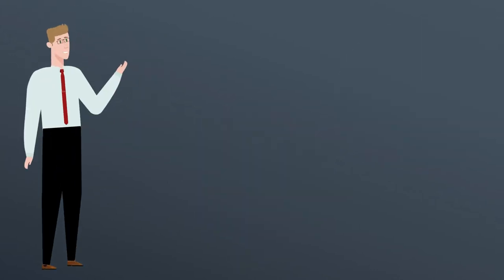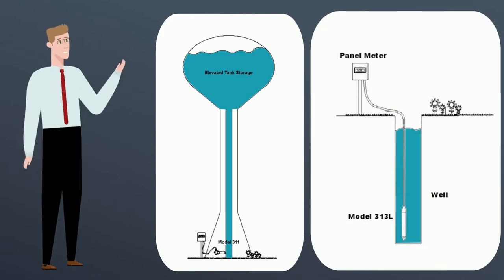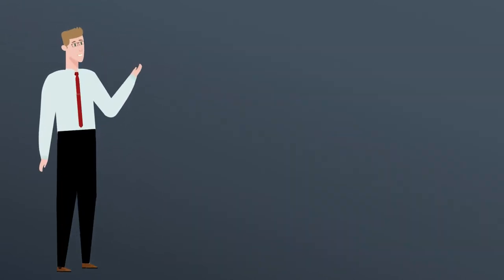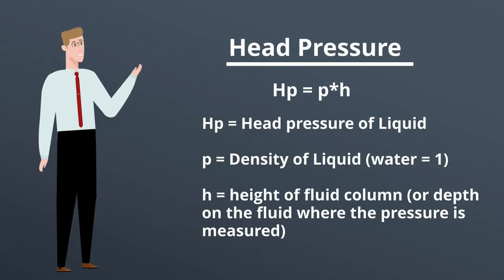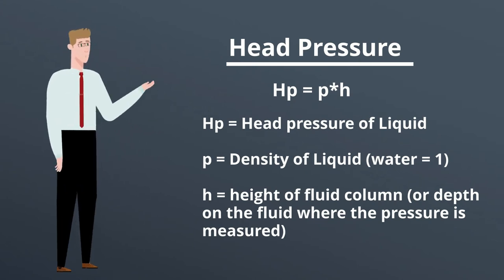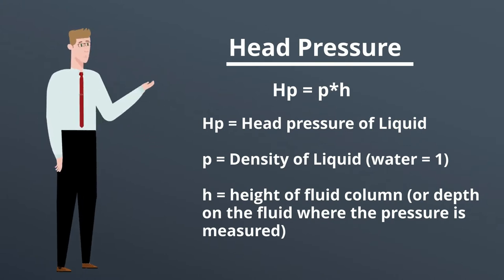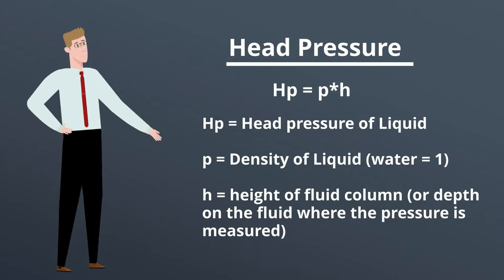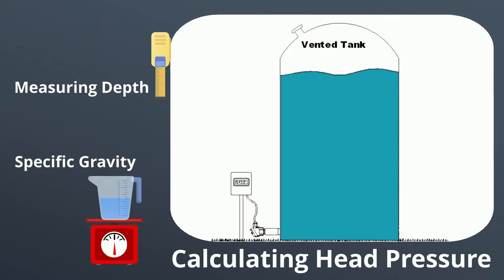These devices function on the same principle of a pressure transmitter by measuring static head pressure. Hydrostatic level sensors use the principle of head pressure. The formula shown provides the pressure range required to measure the depth in a specific tank or well, where head pressure is equal to the density of the liquid times the height of the fluid column or depth in the fluid where the pressure is measured. To calculate head pressure you need to know the measuring depth, typically measured in feet or meters of water, and the specific gravity of the media you are measuring.